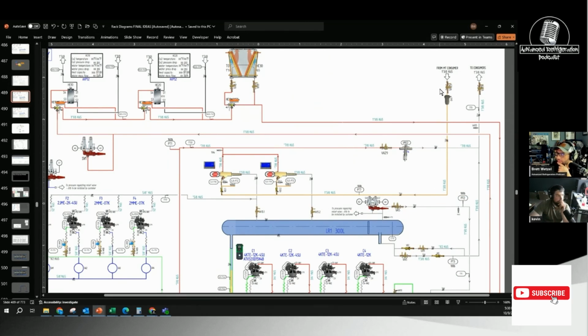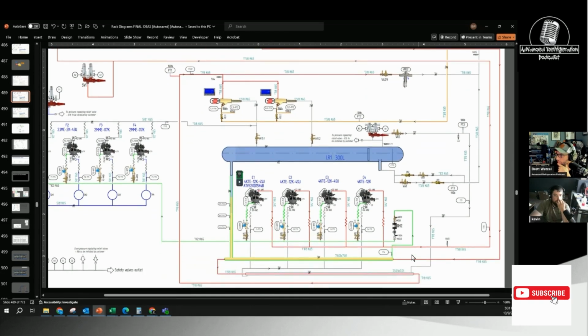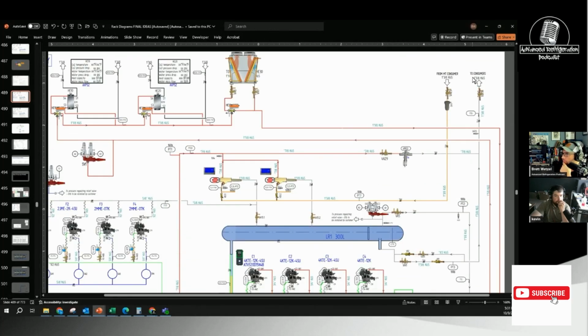Really? Yeah, look. That version would be a lot better, to be honest. Yeah, so look there, and I think, if I'm not mistaken, there's something special about this, and I forget. We walked through this whole thing. There's a ball valve right there, goes down there. It's a suction. So it basically acts almost like, check this out. It pulls, because it's using that all through the ejector. It's pulling the suction gas off the top directly off of here, and then going through here over to the suction, and then basically using that pressure to help push the liquid back out to the cases.